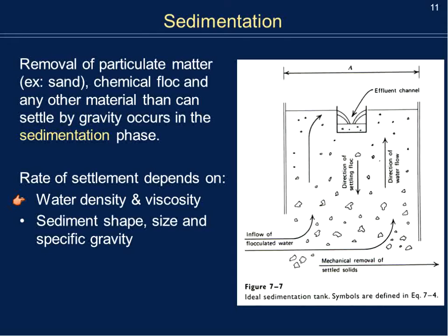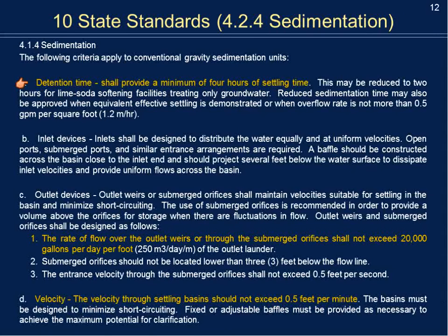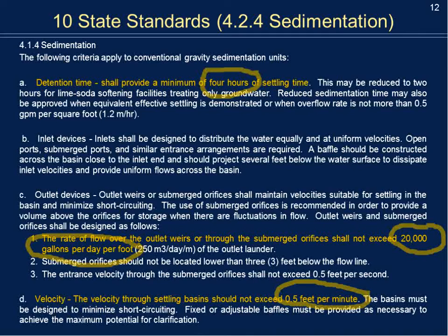The Ten State Standards for sedimentation require: detention time of a minimum of four hours — significantly more than the 30-minute minimum for flocculation. The rate of flow over outlet weirs shall not exceed 20,000 gallons per day per linear foot of weir. The velocity through the settling basin should not exceed 0.5 feet per minute, to allow larger particles the opportunity to settle without being disturbed.